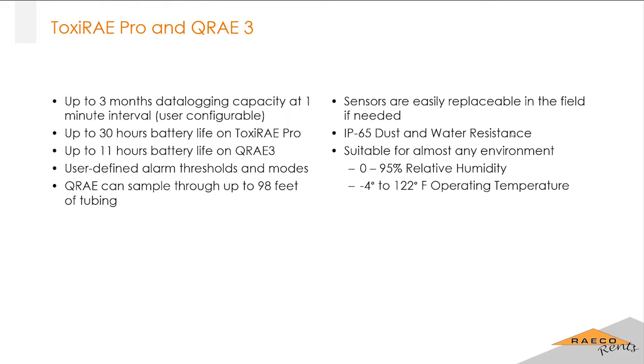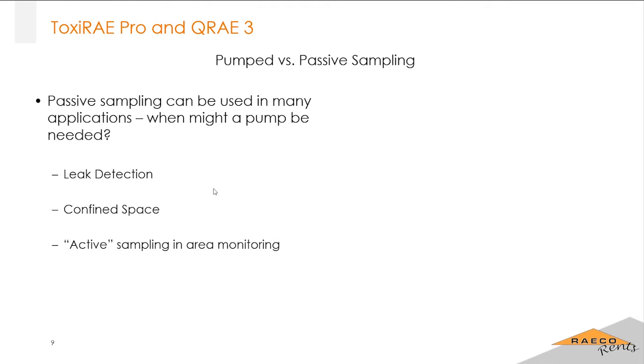They are water resistant, so don't be dropping them in the water, but if they're getting sprayed a little bit, that's okay. And as far as humidity and temperature, you pretty much don't need to worry about that. They're suitable for most environments. All right, so some people may ask, when can I use passive sampling, or when might I need a pump? We went over this a little bit before, but for leak detection in confined spaces, you're definitely going to want to use a pump. You've got to make sure that you're pulling that air, trying to find the leak in this case, or, from the confined space, pulling that air up and making sure that there are safe levels of gases down there.